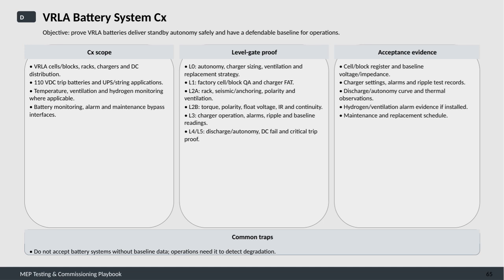It also covers 110 VDC trip batteries and various UPS or string applications. Where applicable, temperature, ventilation, and hydrogen monitoring systems are checked to ensure safe conditions. Additionally, the battery monitoring systems, alarms, and maintenance bypass interfaces are all part of the scope. Moving on to the level gate proof steps.